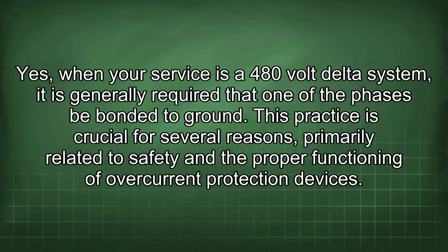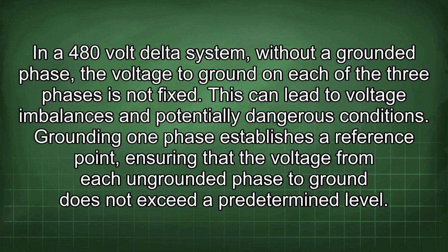Yes, when your service is a 480-volt delta system, it is generally required that one of the phases be bonded to ground. This practice is crucial for several reasons, primarily related to safety and the proper functioning of overcurrent protection devices. In a 480-volt delta system without the grounded phase, the voltage to ground on each of the three phases is not fixed. This can lead to voltage imbalances and potentially dangerous conditions.